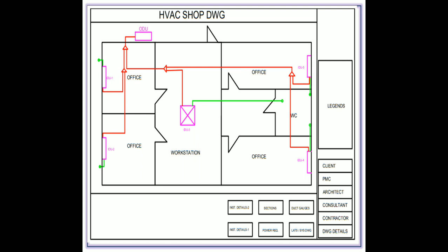Once shop drawing is approved, installation work is started as per shop drawing. Architect collects soft copy of approved shop drawing from each vendor and superimposes all service drawings in one drawing. The drawing which contains all services in one single drawing is called coordination drawing. Architect sends this drawing to each vendor and asks to check if there are any clashes occurring. Sometimes fire pipe comes in the route of AC duct, or electrical light and supply air diffuser are shown in the same place, or ceiling is up and duct coming down the ceiling. To avoid all such problems, coordination drawing is required. In this way, work is pushed on site.